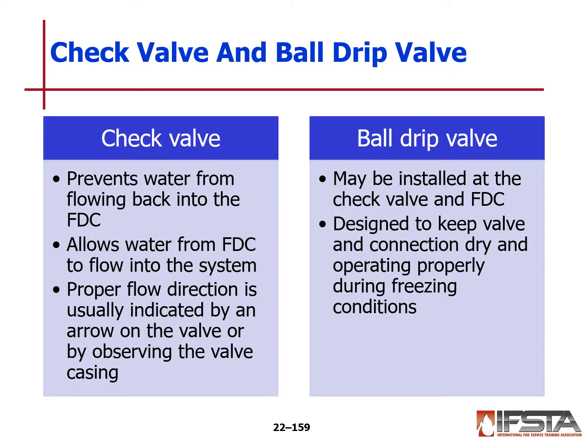Check valves and ball drip valves. Your check valve will prevent water from flowing back into the FDC. This allows water from the FDC to flow into the system. Proper flow direction is usually indicated by an arrow on the valve or by observing the valve casing. The ball drip type may be installed at the check valve of the FDC. This is designed to keep the valve and the connection dry and operating properly during freezing conditions.